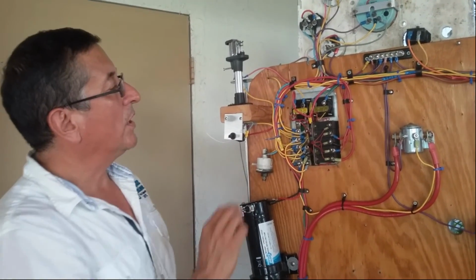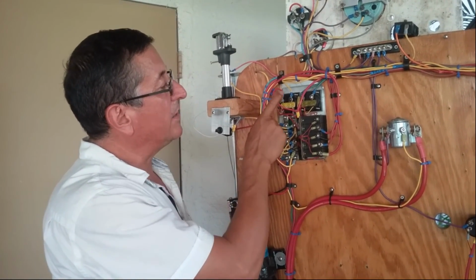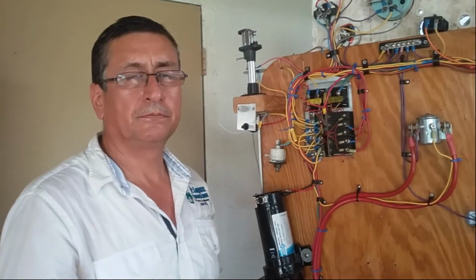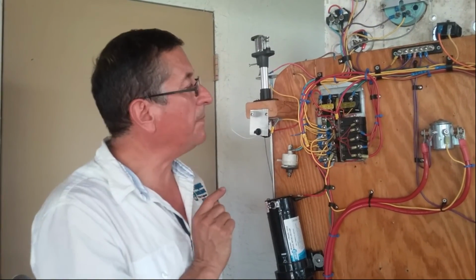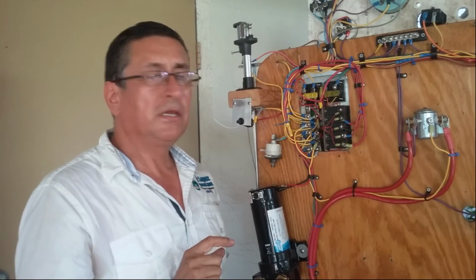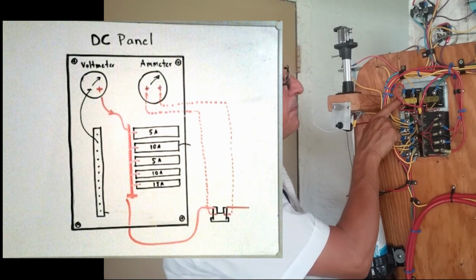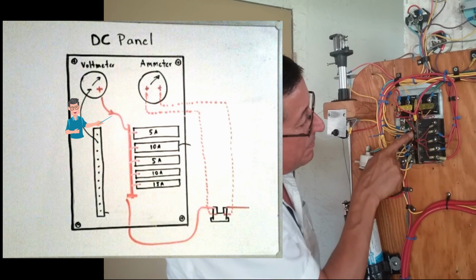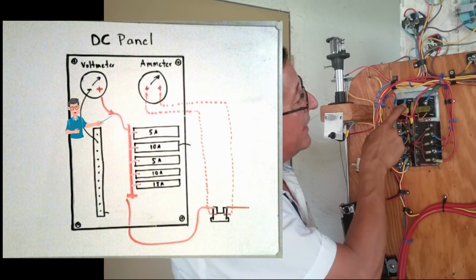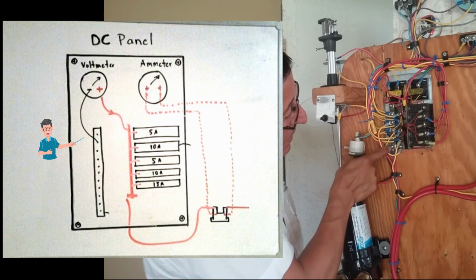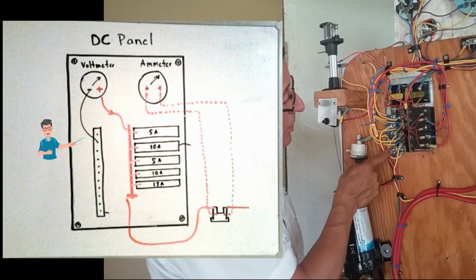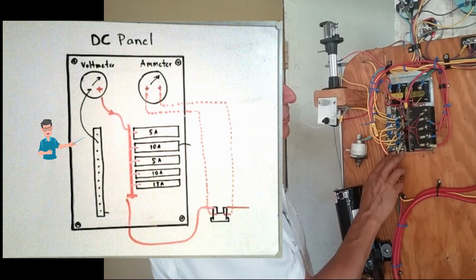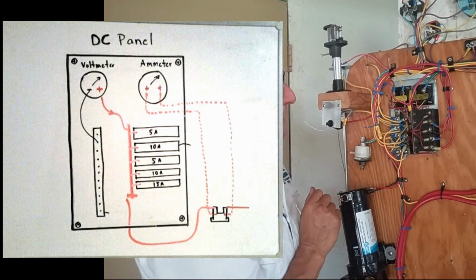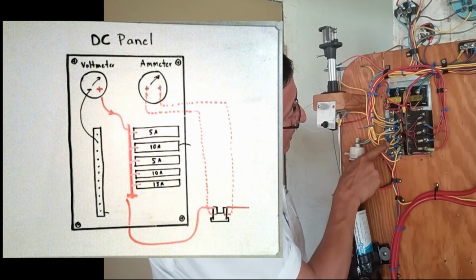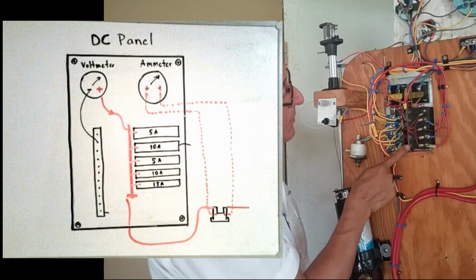All right, right now I am going to explain the procedure to install the voltmeter and the ammeter. If you remember, in a previous episode I explained that the voltmeter for a DC panel should be connected with the positive to any part of the positive bus bar, and the negative to any part of any negative bus bar. In this particular case, this negative bus bar, because it's pretty close to the panel. Okay, the negative to the negative bus bar, and the positive here on the positive bus bar. And right now the voltmeter is working.